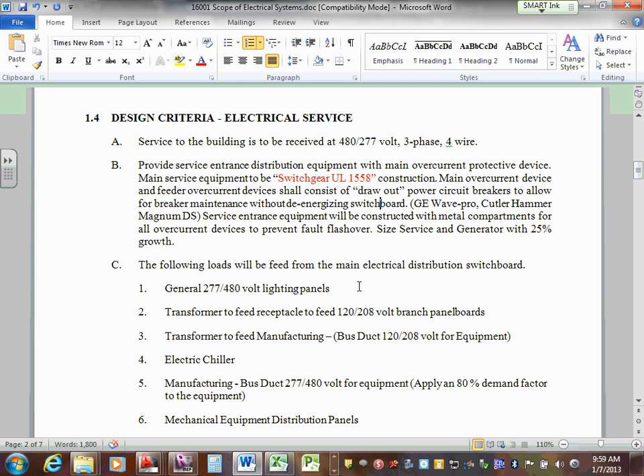We aren't going to be putting 30, 60, or even 100 amp breakers, if we can avoid it, in that big gear with the draw out and the metal clad. It's a fairly expensive location for smaller breakers. So we tend to bring larger blocks of power out of that gear into other methods of distribution.